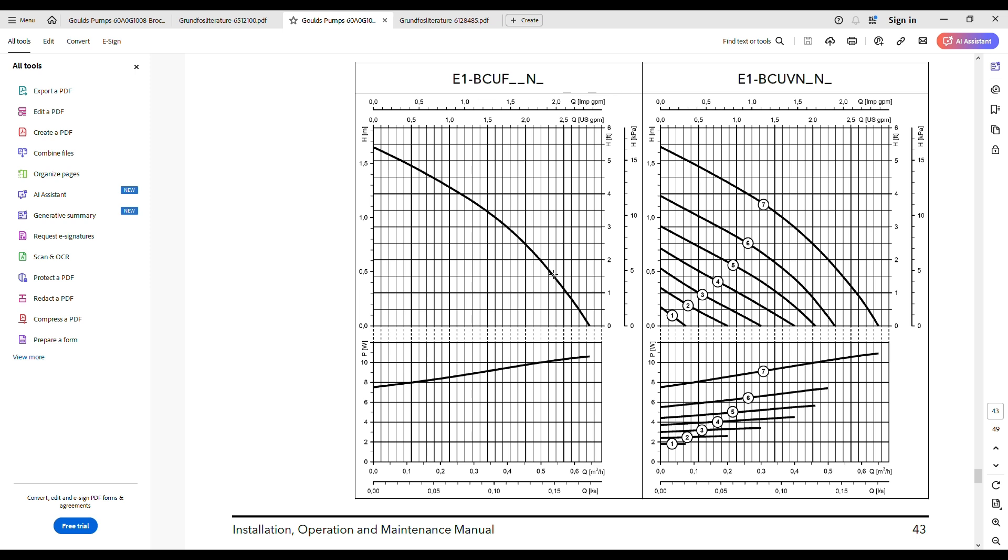I'm not 100% sure if it was cavitation, but I put it in just as an additional safeguard. And what I did find is once I closed the valve down a little bit, the tinkling noise went away. So I think I was probably way over here at the maximum flow and I've just brought it back a little bit by closing that valve down a bit. And now the pump seems to be much quieter, and so now when it runs it just hums. There's no additional noise. So that's the reason for the outlet valve, the extra valve that I put on the pump.